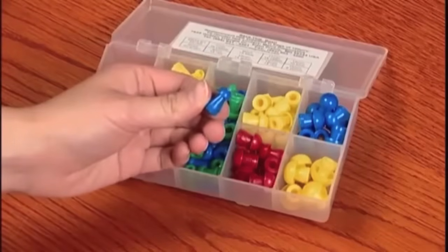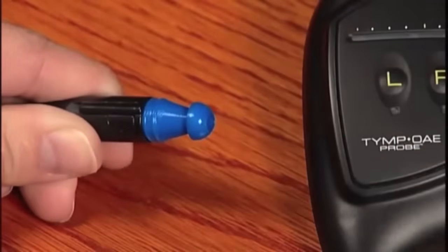After selecting the proper ear tip, push it onto the probe tip until it is flush against the base. To remove it, grasp the ear tip at the base and twist it while pulling it straight off the end of the probe tip. To ensure the patient's safety and a proper fit, you should only use the ear tips that are approved for use with the Ero Scan Pro. Contact your distributor or Maico for ordering information. Remember, the ear tips are disposable and should be replaced after each patient. Please do not attempt to clean or reuse these ear tips, as this poses a potential risk and can lead to erroneous test results.